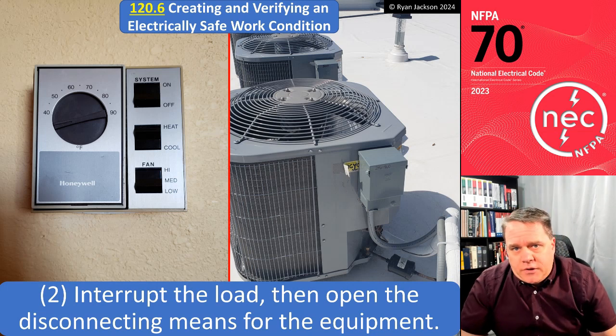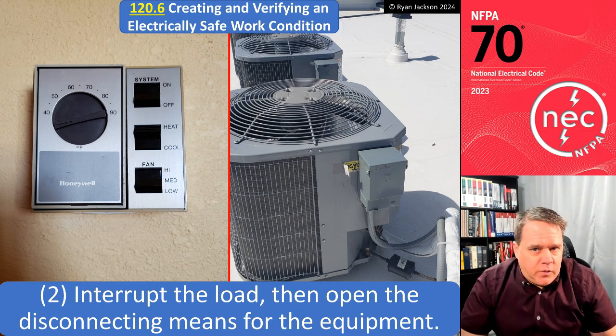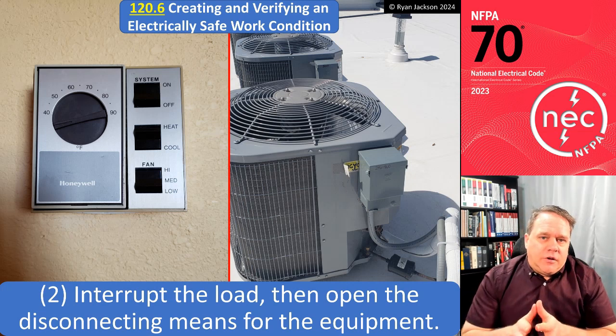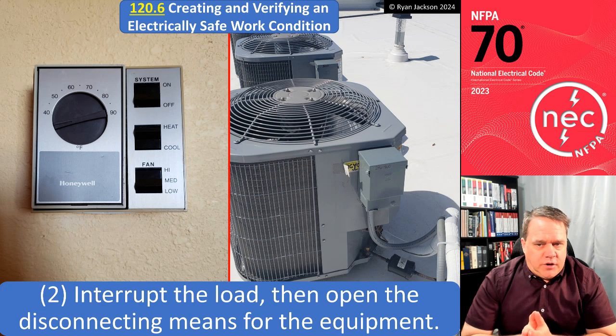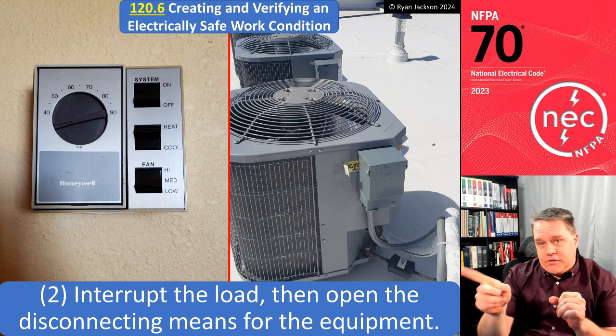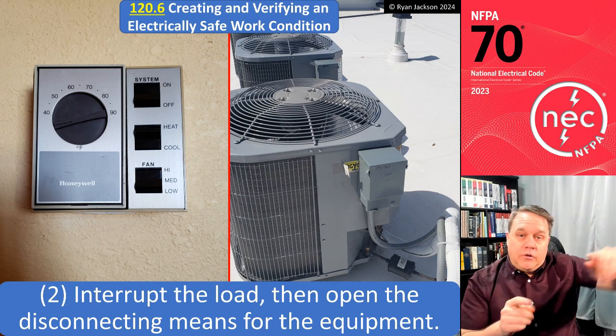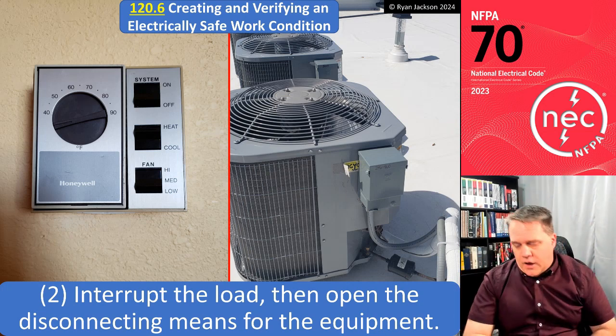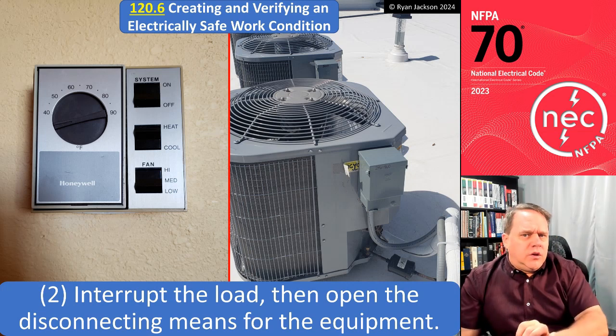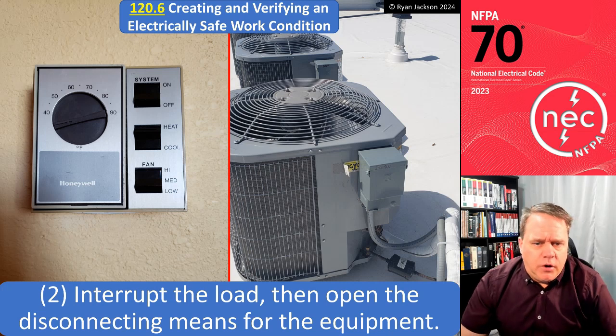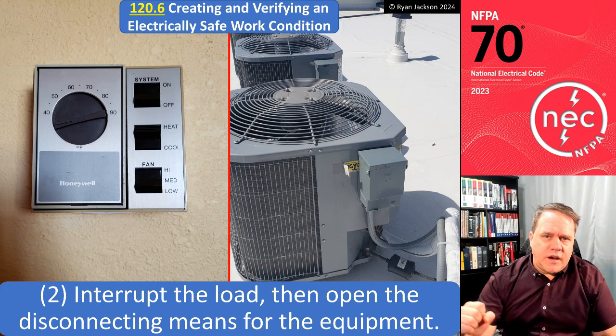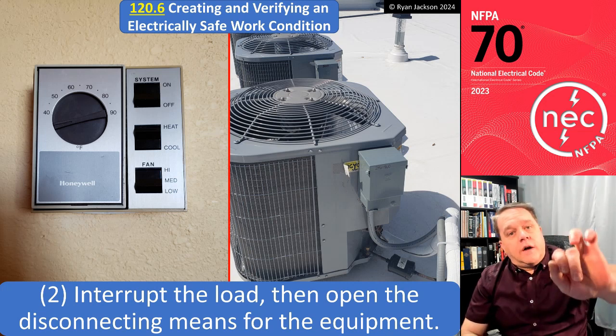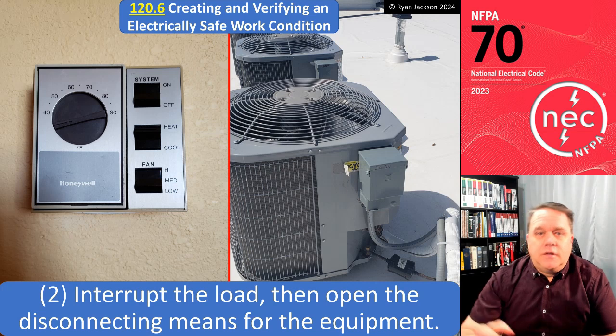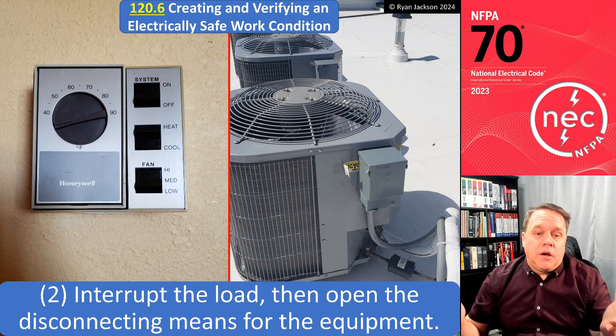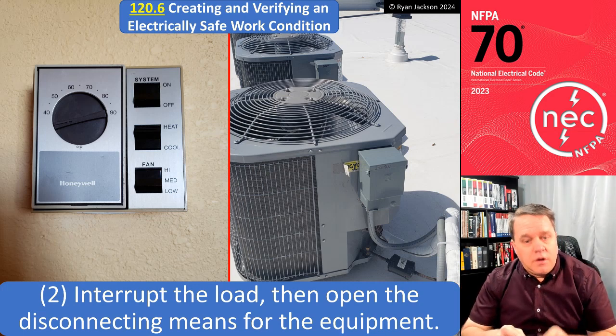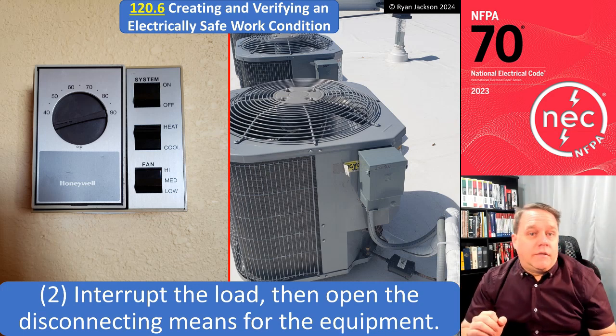Item 2, interrupt the load, then open the disconnecting means for the equipment. All right, so once I've figured out what circuit supplies this air conditioner, because maybe I need to work on the supply side of this air conditioner, maybe shutting off the breaker, or working on the supply side of the disconnect, changing fuses, I might have to shut off the breaker. What if I'm working on the unit? Well, shutting off the disconnect might be all that I need to do. But which would be better? Shutting off the disconnect while the motor's spinning, or shutting off the motor by turning off the thermostat and then opening the disconnect? Yeah, probably a better thing to do would be to interrupt the load, then open the disconnect, right? So shut the motor off at the thermostat.